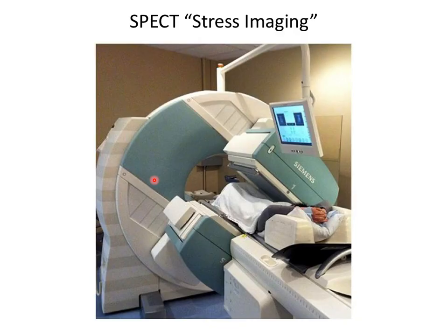And so here's another example of a geometry where you have detection on one side and 180 degrees around you have detection on the other side. You could imagine there could be another detector here. You just try and load up detectors so you catch all the photons that are coming out. And then this whole gantry here rotates, okay? And this section here is probably the CT section of this scanner.